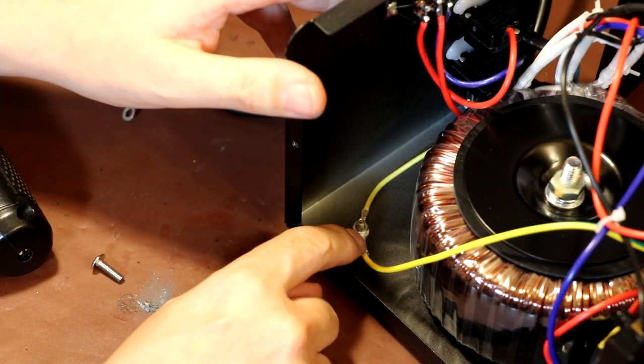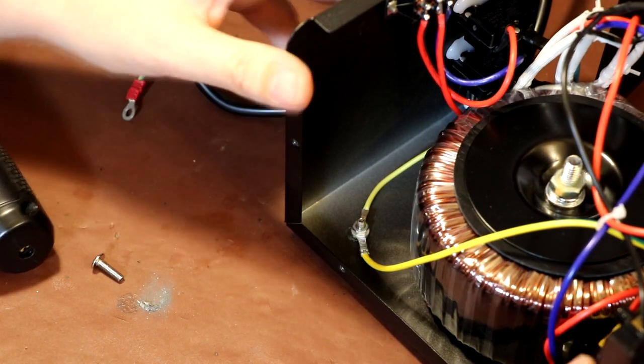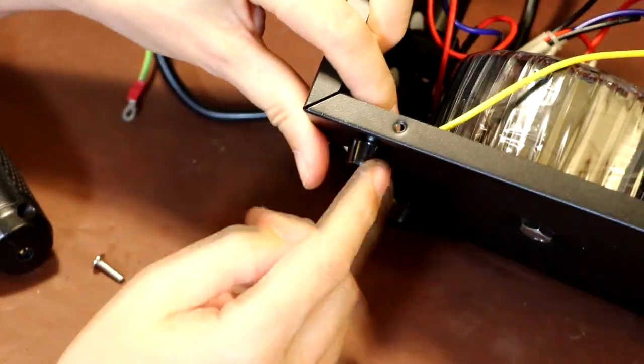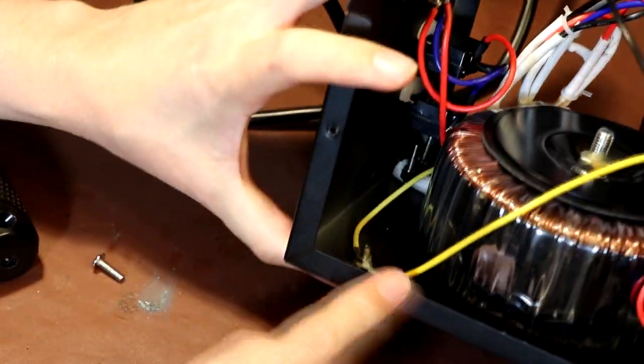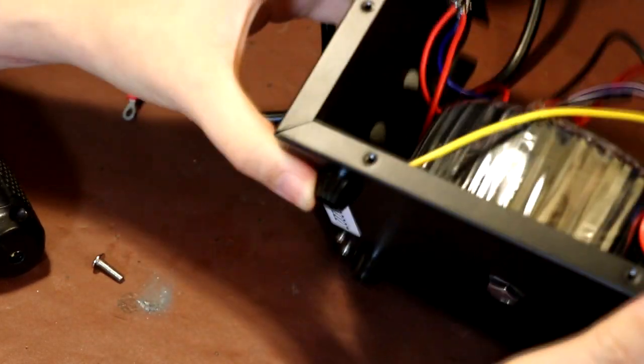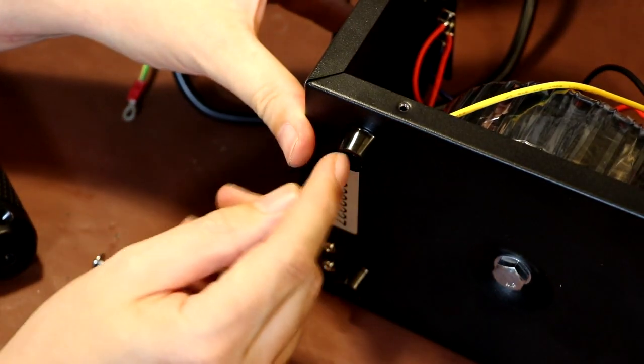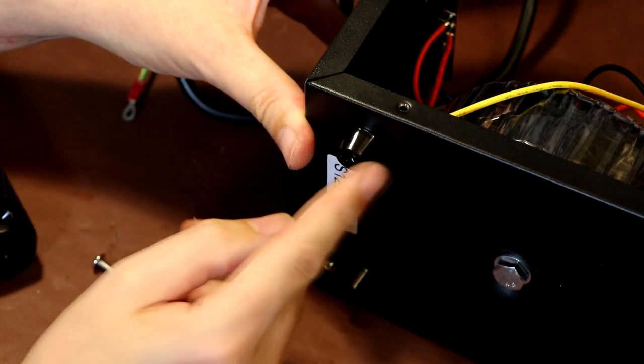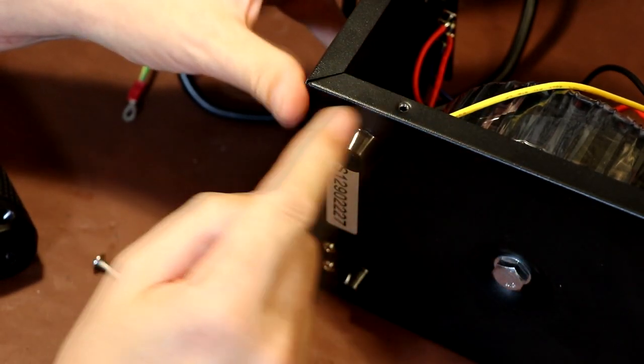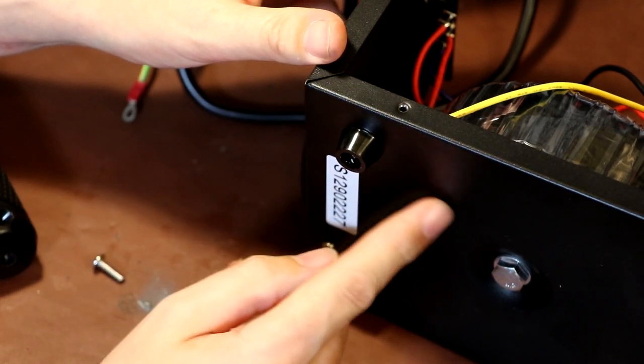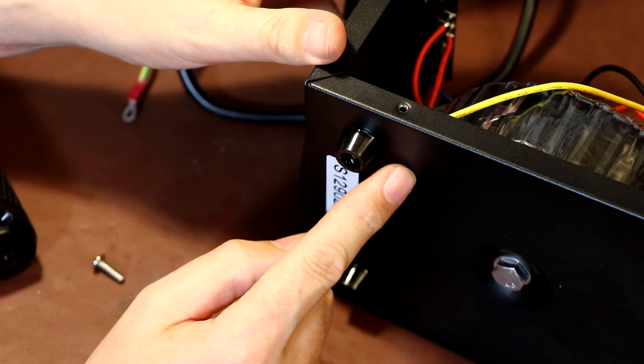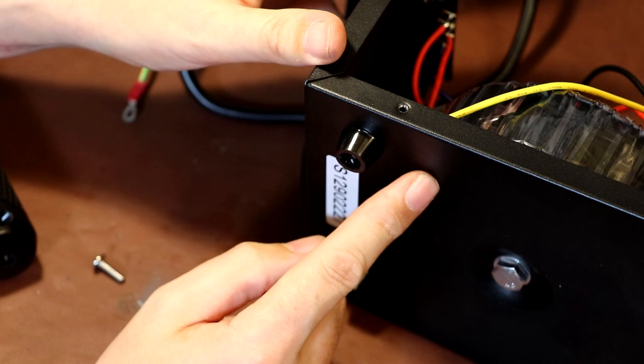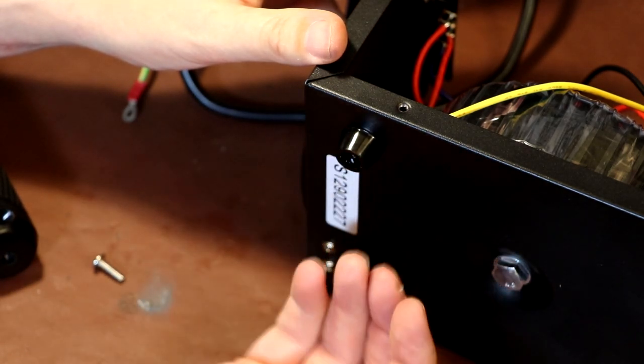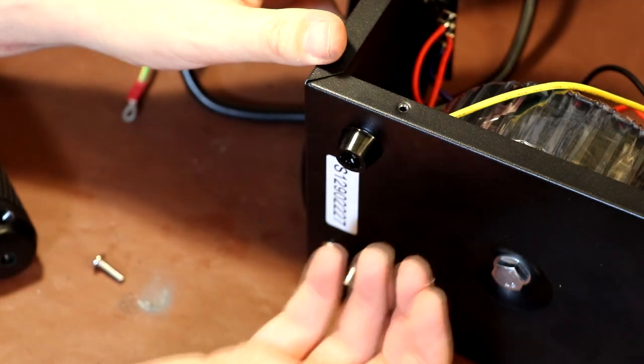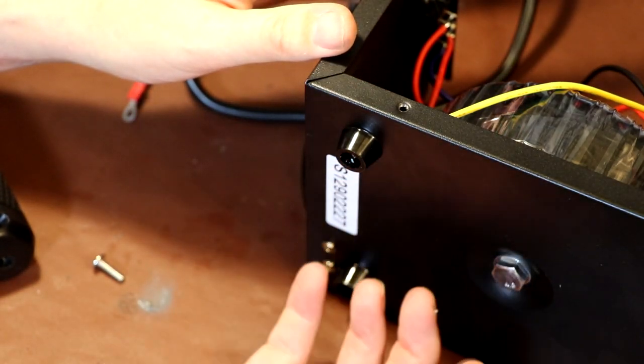I was just about to remove this bolted connection to fit our new earth wire, and when I tipped up the equipment I noticed that the earth wire doesn't go to a bolt on the bottom. What it's actually going to is one of the feet. Now that is not correct. It's part of the legislation, I'm pretty sure, that says if you're using an earthing stud, it has to be a dedicated earthing stud. It can't just be a bolt that's holding the case together. The rationale is that somebody could lose or knock the foot off, and if they did, they would lose the earthing on the piece of equipment.